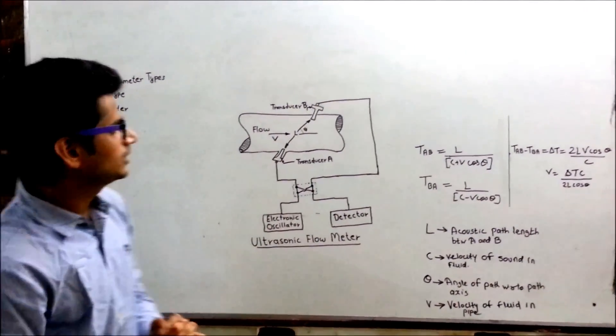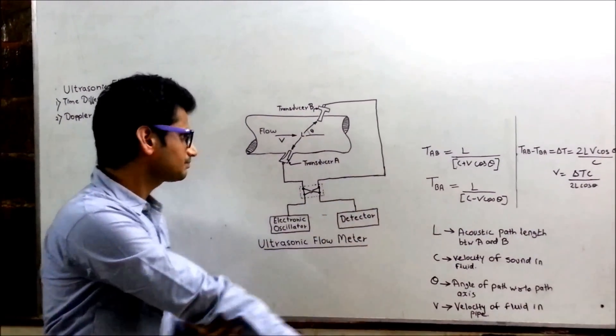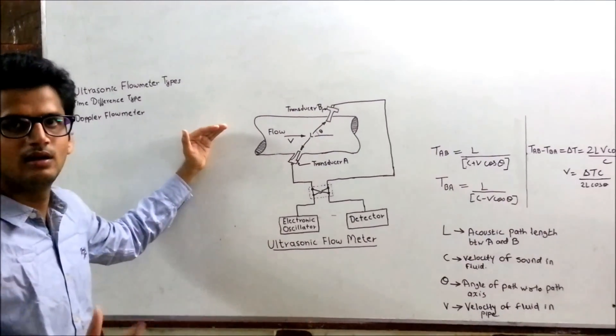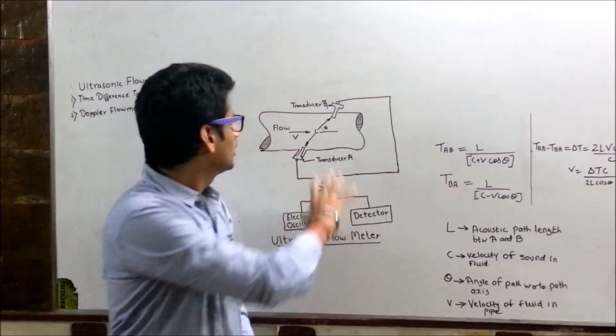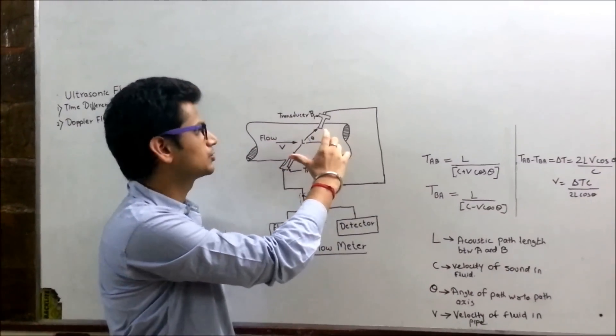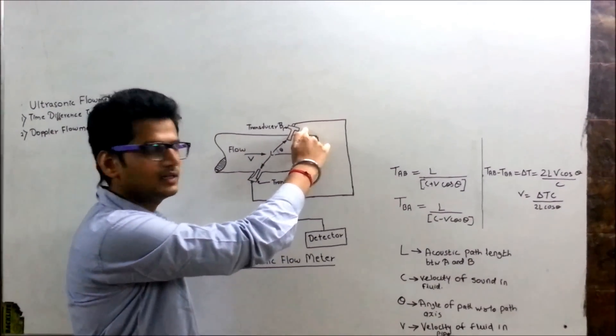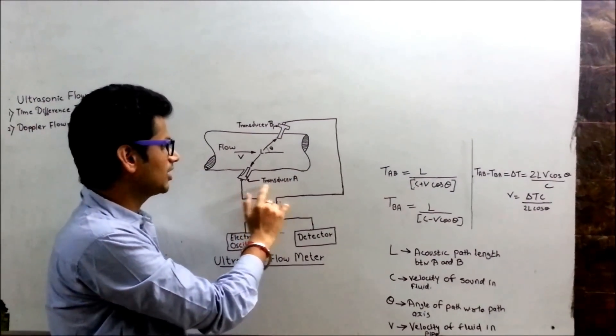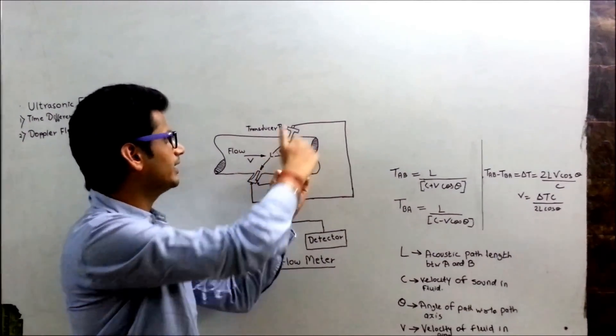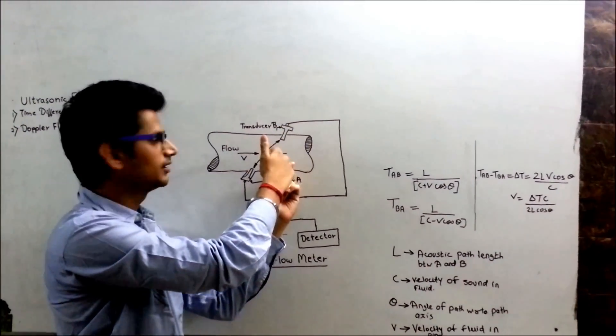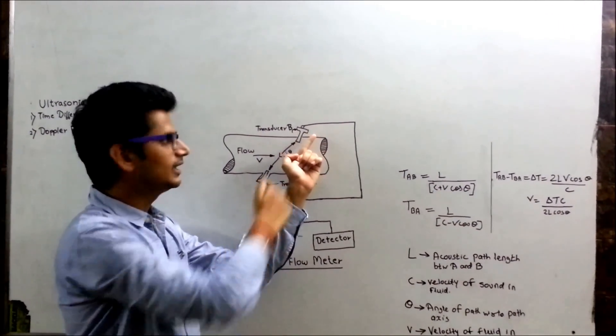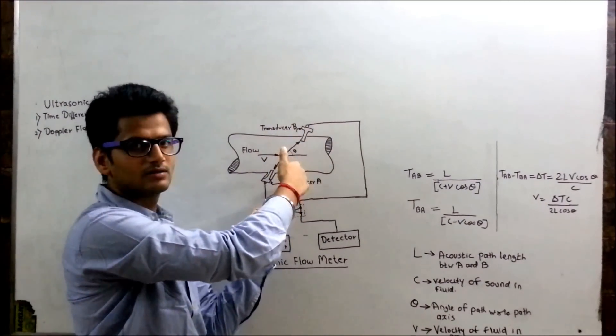Now, I will explain the working, how it exactly works. The fluid will pass from the pipe. The fluid may be gaseous, liquid, anything. There are two transducers installed over here, one at the upper side and one at the lower side. This is transducer A and transducer B. Both the transducers will transmit and receive the signal vice versa. Once transducer A transmits the signal, B will receive. Then B will transmit the signal and A will receive.